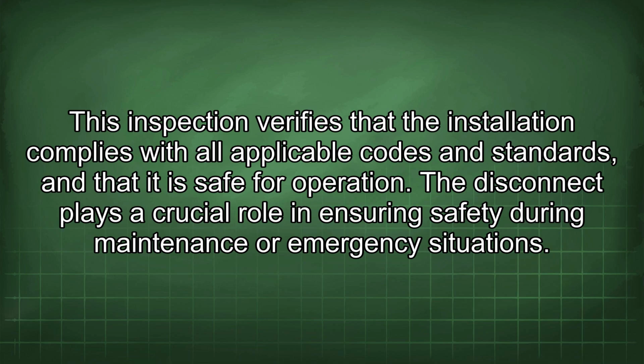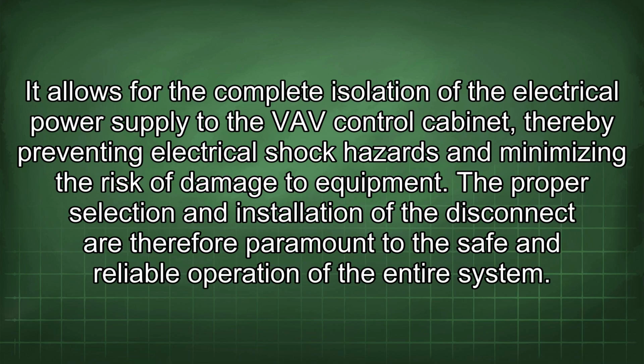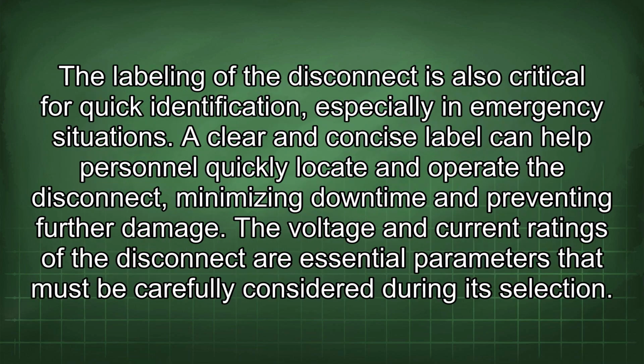The disconnect plays a crucial role in ensuring safety during maintenance or emergency situations. It allows for the complete isolation of the electrical power supply to the VAV control cabinet, thereby preventing electrical shock hazards and minimizing the risk of damage to equipment. The proper selection and installation of the disconnect are therefore paramount to the safe and reliable operation of the entire system. The labeling of the disconnect is also critical for quick identification, especially in emergency situations.